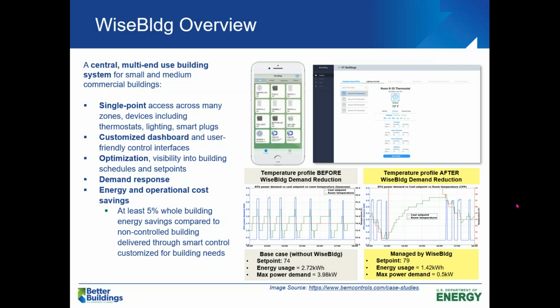On the lower left here, what I'd like to highlight is a case study that BEM Controls has provided with the link below that shows a customer that was having a hard time trying to mitigate peak demand costs. And you see the blue line there on the left plot is the demand curve, and around every hour or so the AC was cycling on and off. So BEM Controls data on the right you can see widened the set points during that peak demand time and really substantially cut the peak demand during that peak demand window from 4 kilowatts all the way down to half a kilowatt.